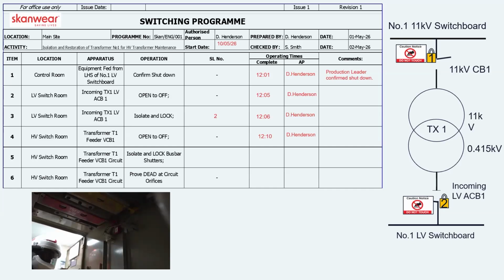But yeah, for this example, we're going to lock those shutters so people can't come into contact with the live 11 kV bus bars. I'll then update my switching plan to say when it was done, my safety lock number, and that it was me as the authorized person. We're now going to prove dead. So the typical process for work on MV or HV is isolation: disconnection from all sources of supply with sufficient air gap to prevent re-energization. We're going to positively maintain that by applying a lock so it can't be re-energized.